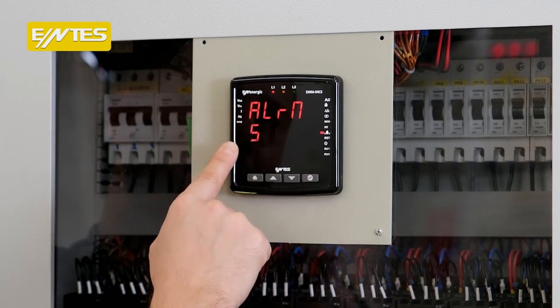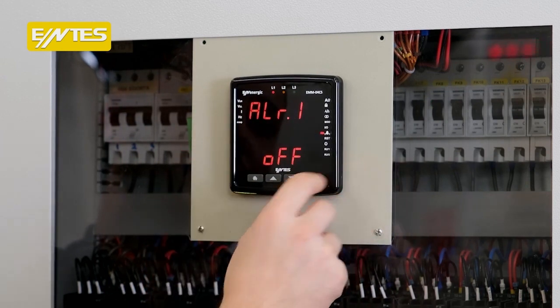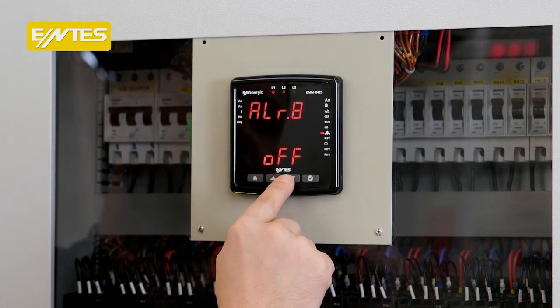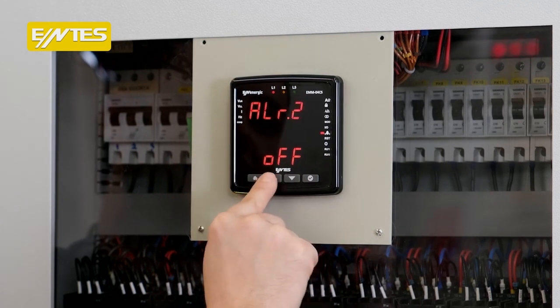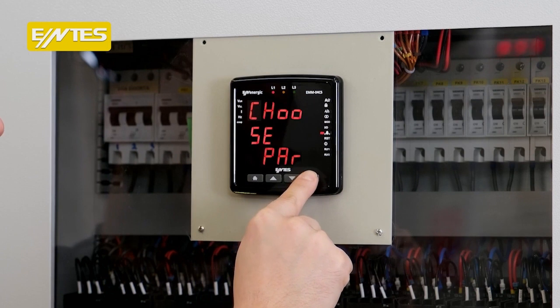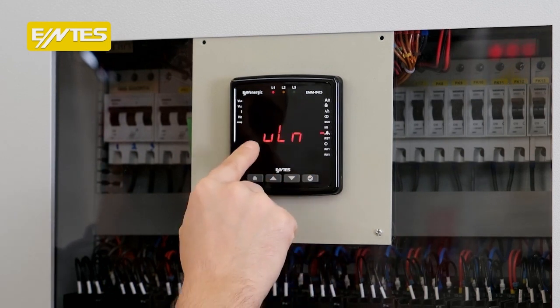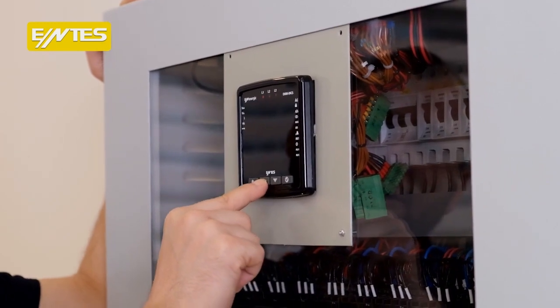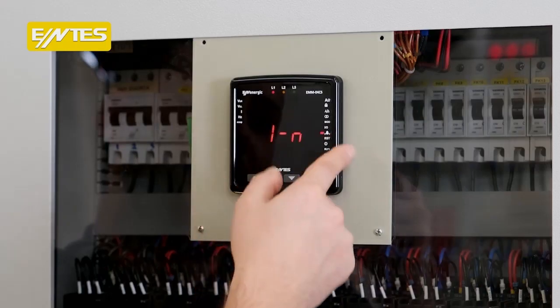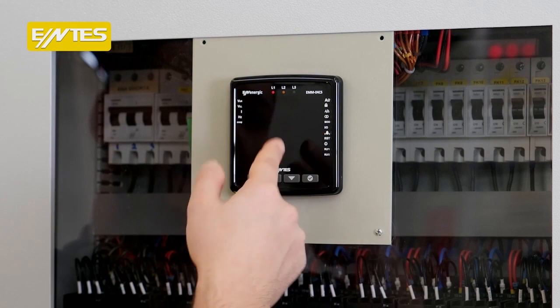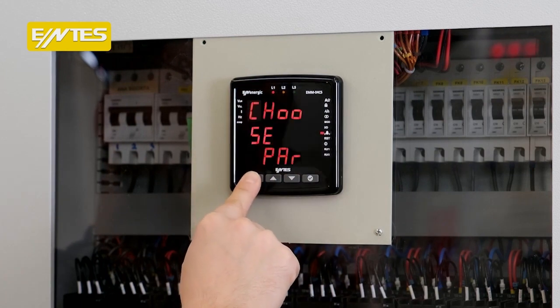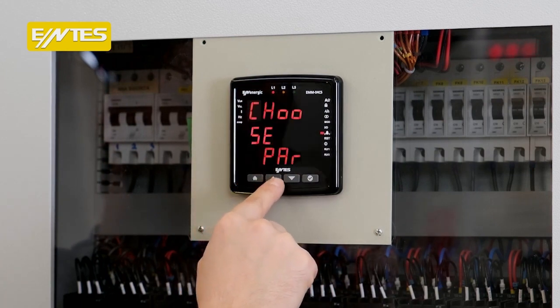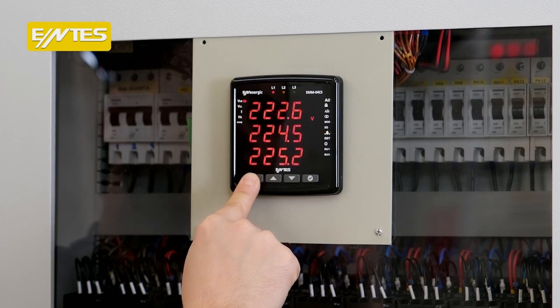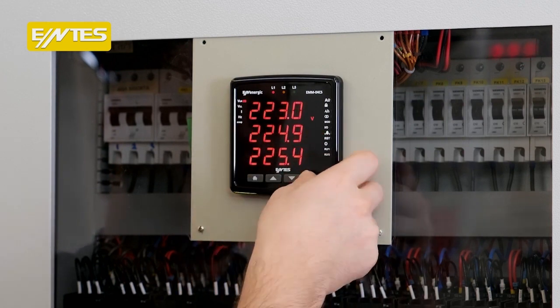We have the option to create an alarm from this alarms menu. Here, the device is currently set to a total of 8 alarms. We set the first alarm, we pick parameters. Look, here it's asking for a parameter from us. Here we can create our alarms by selecting parameters such as phase, neutral, current, and neutral currents from here. If we make a modification on the device, we must save it by navigating back using the home button.